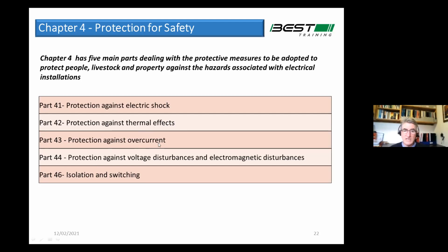Protection against overcurrent, no real changes there to the best of my knowledge that I'm aware of. So that's just a standard thing about how to select a protective device, you know, fuse, circuit breaker, etc., and the relationship between that and the conductor cross-sectional area. So nothing really changed in that. The next section is massive changes on it. It's really, really big, 35 pages, I think, in total, versus a half page in the 4th edition. And then isolating and switching, again, I don't think there's any major change in that.